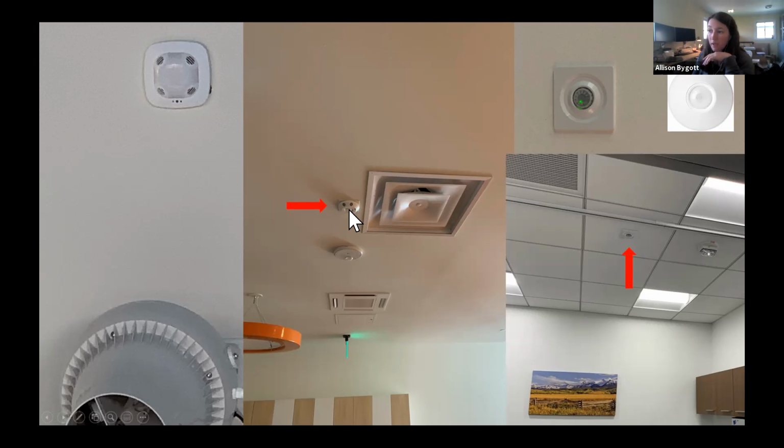This sensor also has an LED indicator light under the lens. If they're battery powered, they don't turn them on. They don't want to waste the battery. So you have this sensor in the ceiling and somebody has to decide, did it get placed there? Is it actually wired? Is it working?